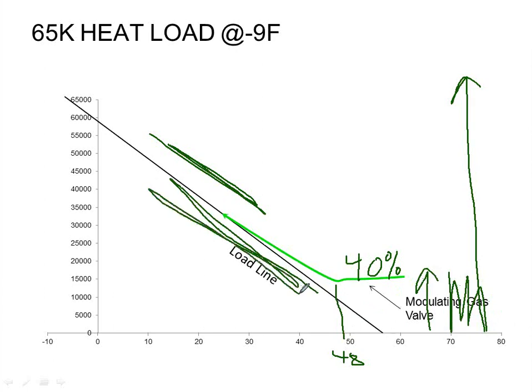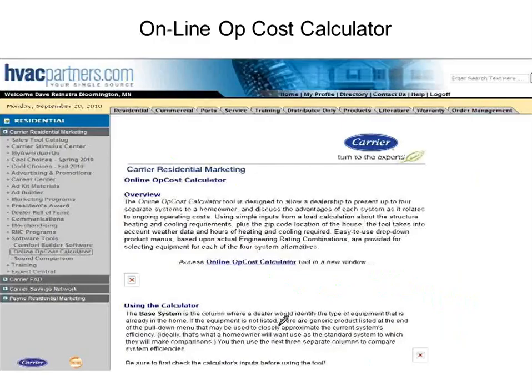The more oversized you make the person's furnace, the more it's going to have to cycle on and off even though it's a modulating gas valve because it only can go down to 40%. So getting the furnace correctly sized is more important than ever with a modulating furnace or even a modulating boiler. Oversizing is not more forgiving because it's modulating. It's actually worse. So do not oversize the furnaces or boilers. Get them correctly sized for the application, and then let the modulation just help you make things more comfortable.